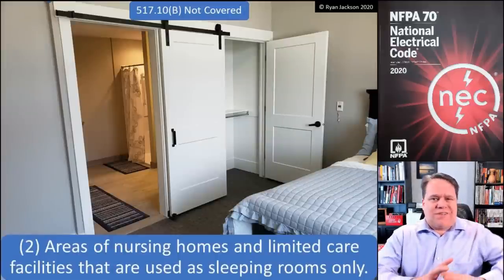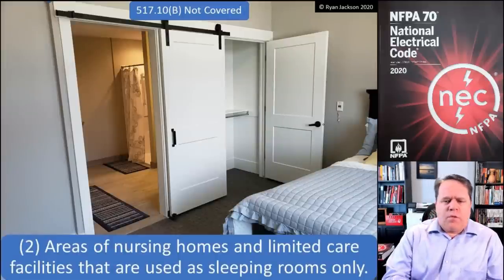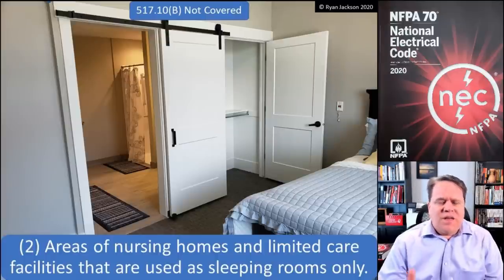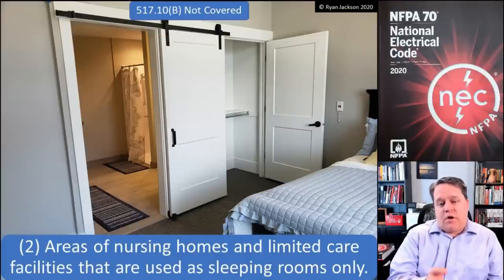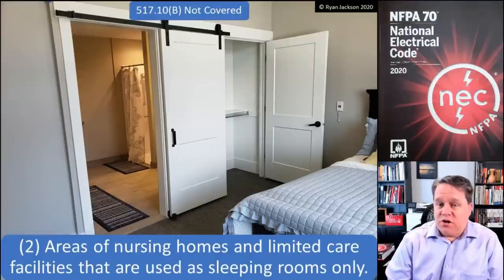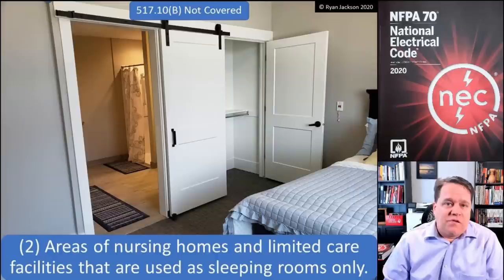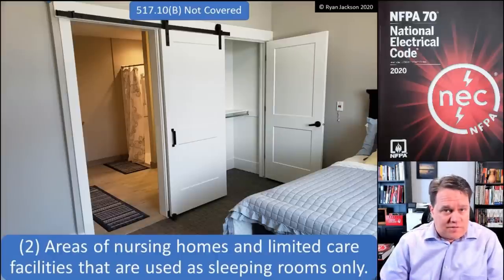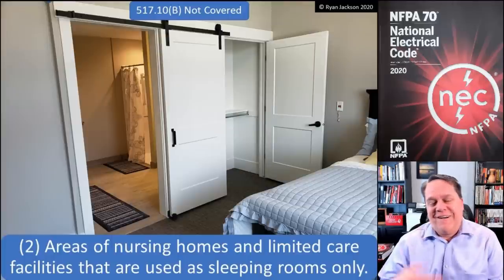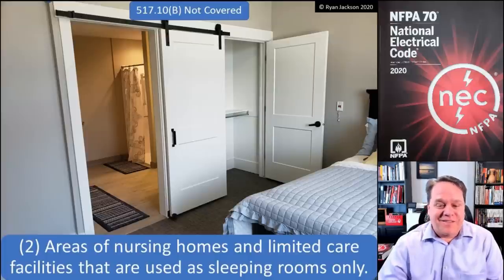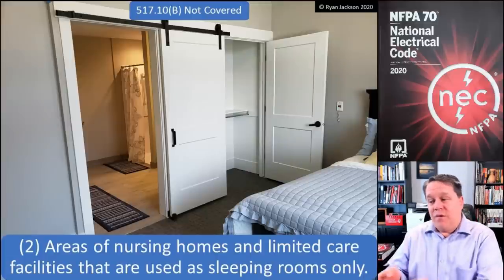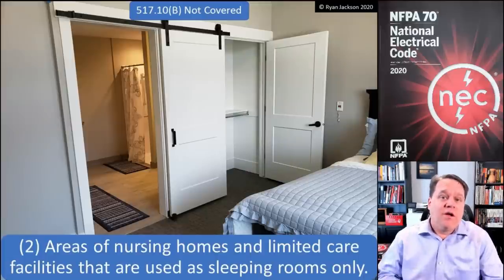That conversation gets more nuanced with item two: areas of nursing homes and limited care facilities used only as sleeping rooms. Is that a patient care space? Not if they're only used as sleeping rooms. But if they're also used as rooms to examine and treat the patient, then obviously they are a patient care space. In a nursing home or limited care facility, individual rooms might just be for sleeping, while a full doctor's office inside the building would be the patient care space.